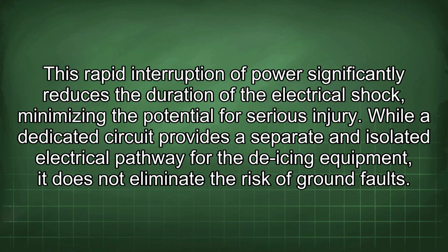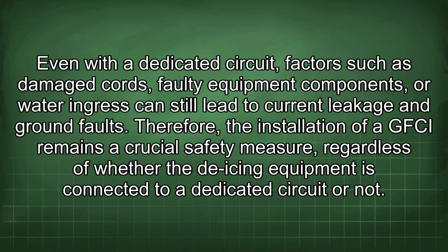While a dedicated circuit provides a separate and isolated electrical pathway for the de-icing equipment, it does not eliminate the risk of ground faults. Even with a dedicated circuit, factors such as damaged cords, faulty equipment components, or water ingress can still lead to current leakage and ground faults. Therefore, the installation of a GFCI remains a crucial safety measure, regardless of whether the de-icing equipment is connected to a dedicated circuit or not.